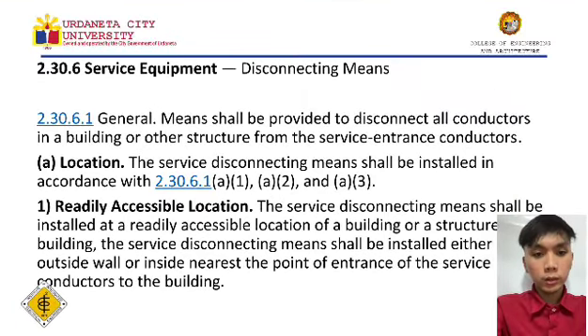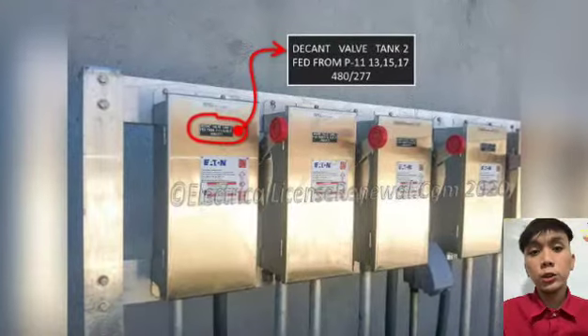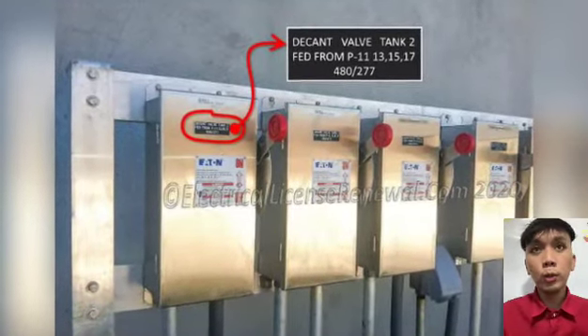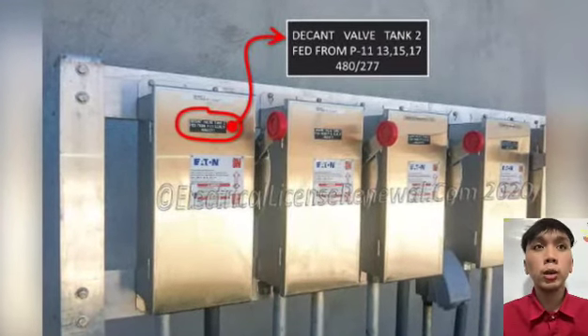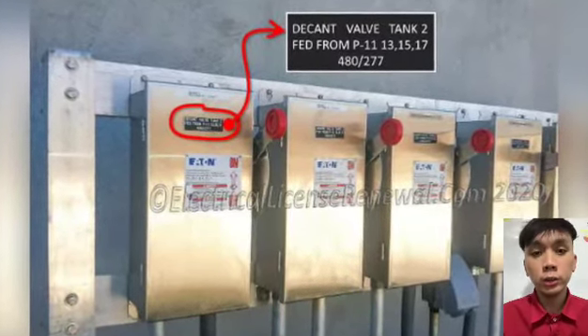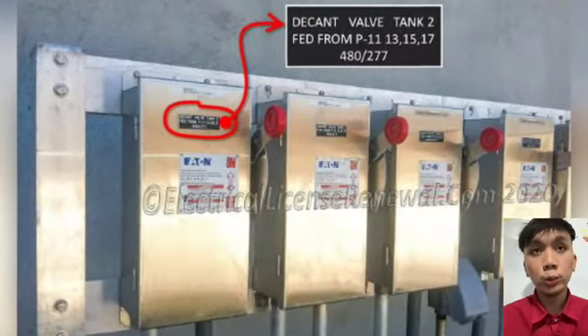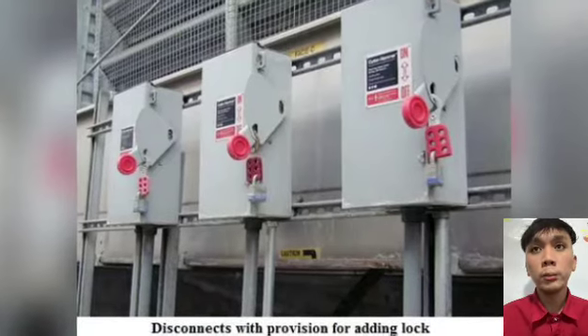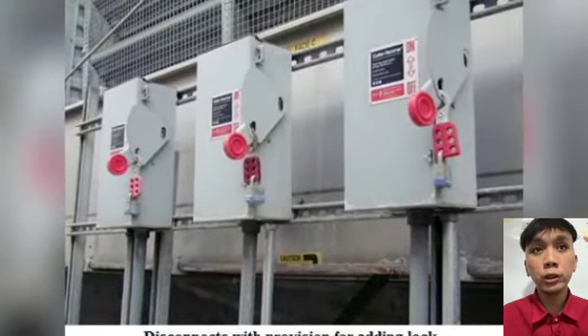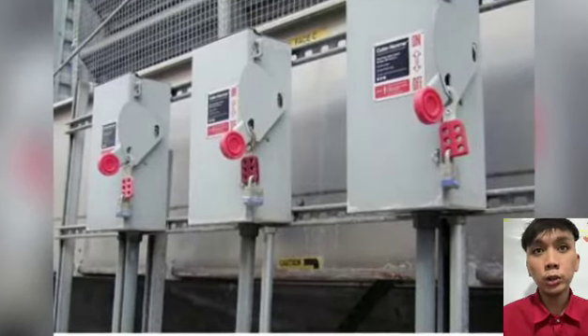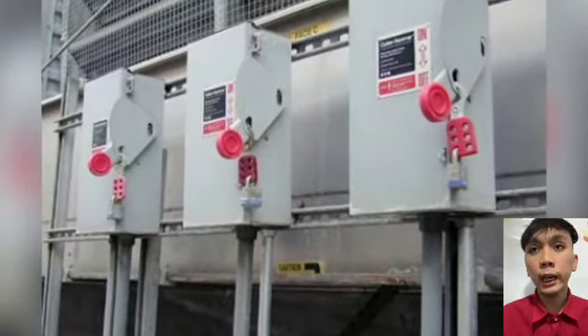Moving on, the service equipment disconnecting means. Means shall be provided to disconnect all conductors in a building or other structure from the service entrance conductor. A disconnecting means is a device or a group of devices or other means by which the conductors of the circuit can be disconnected from their source of supply. This can include a switch, a circuit breaker, a cord and plug connection, or a group of the aforementioned devices. There are other stipulations within the code that dictate how these devices can and cannot be used.